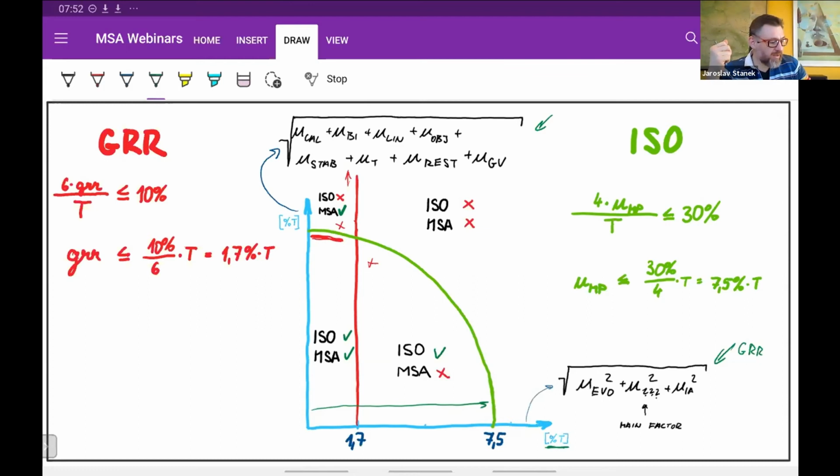If the repeatability is very good in individual appraisers, then we can allow a little higher variation in between the appraisers. Or if the device is very robust to the change in the temperature, then we can allow a little wider range for the repeatability.